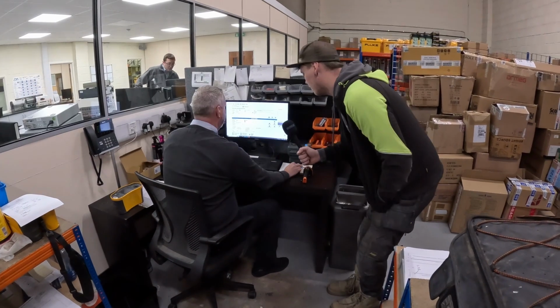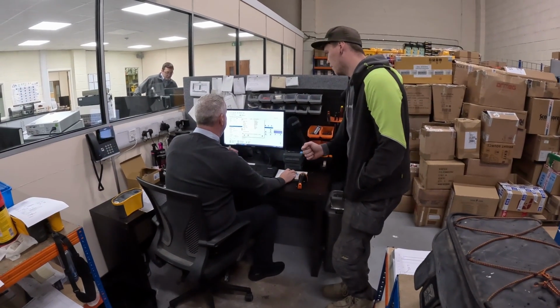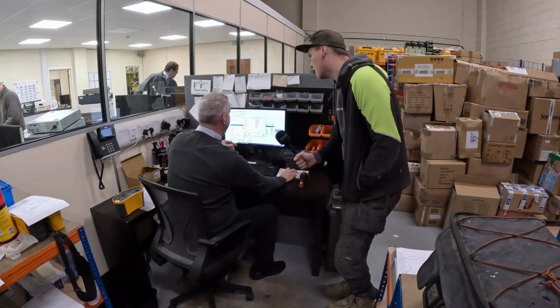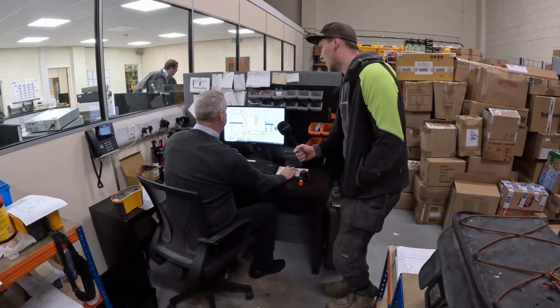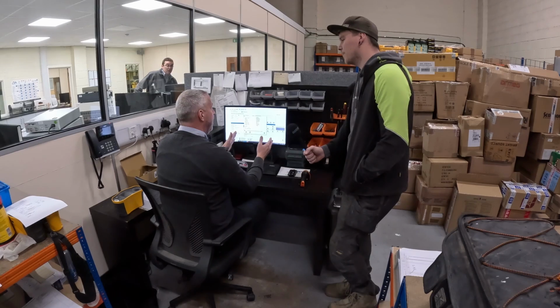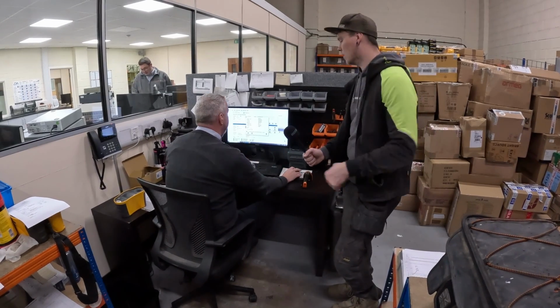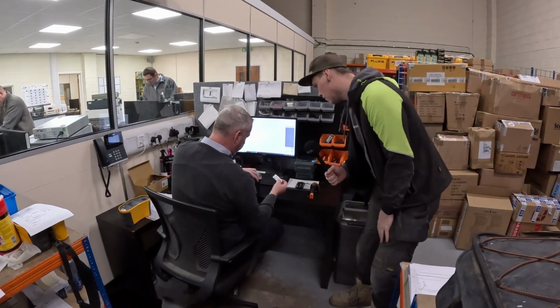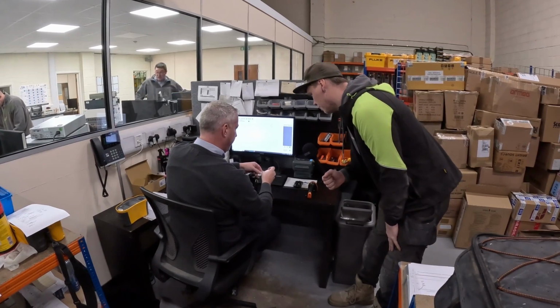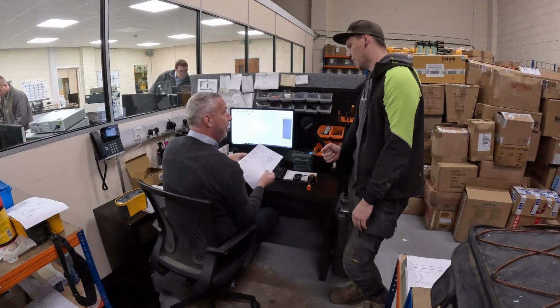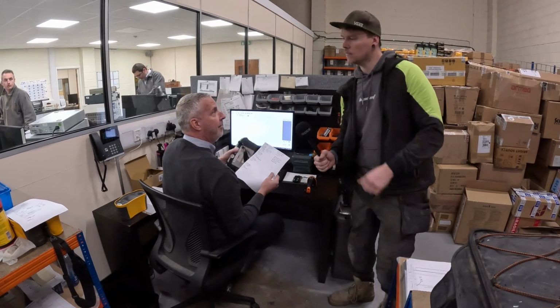And basically we'll check what it's coming with - any accessories, so if it's coming with your three-way test leads, your mains lead. So anything it gets booked in with, when it leaves, it all gets checked back out with it. Every job then gets issued a job number, that gets popped onto there to identify your instrument while it's in here. A job sheet is issued, then the meter goes through to the calibration lab.